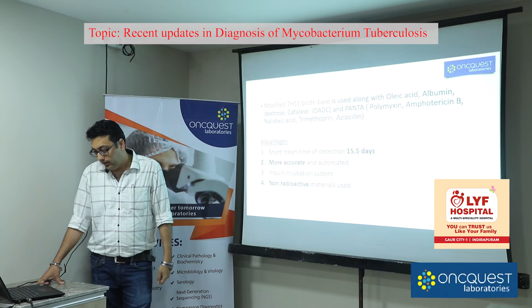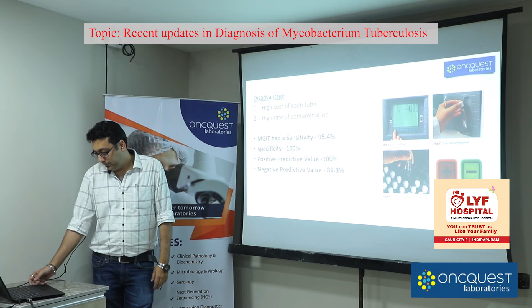Advantages: a short mean time of detection, around 15.5 days, more accurate and automated. There is an inbuilt incubation system, so we don't have to take out the vials again and again, and non-radioactive materials are used. Disadvantage: there is a very high cost of each tube and a high rate of contamination. It has a sensitivity of around 95.4%, specificity around 100%, the positive predictive value is again 100%, negative predictive value is around 89.3%.